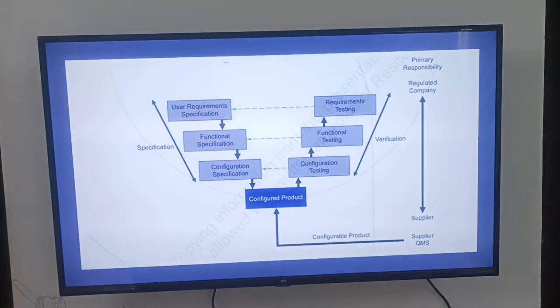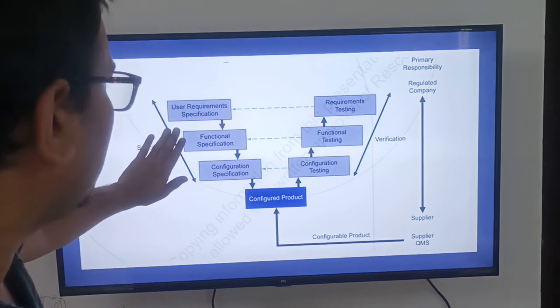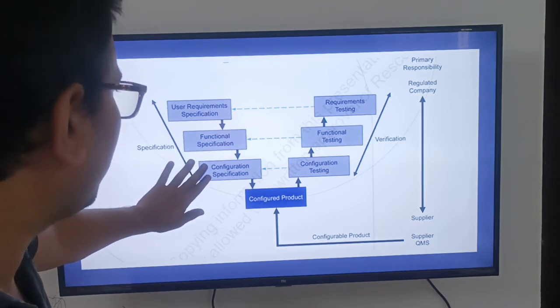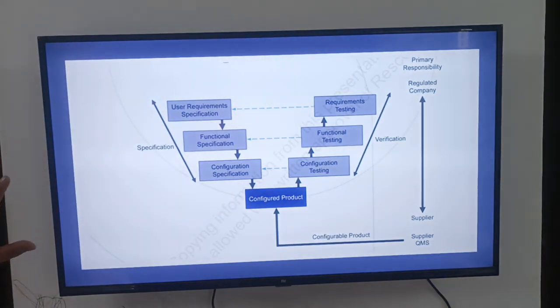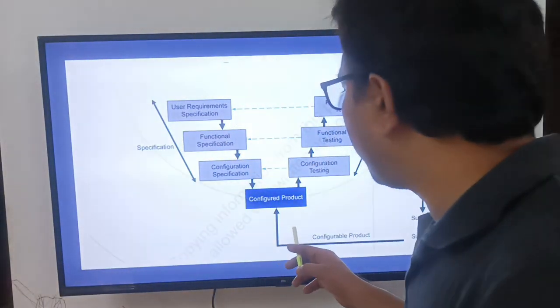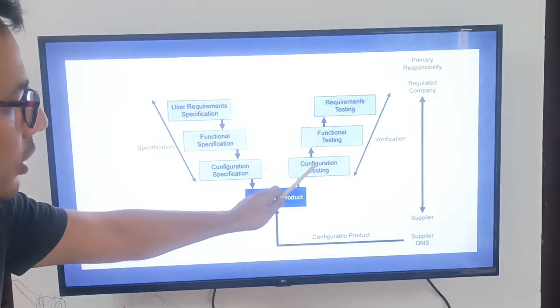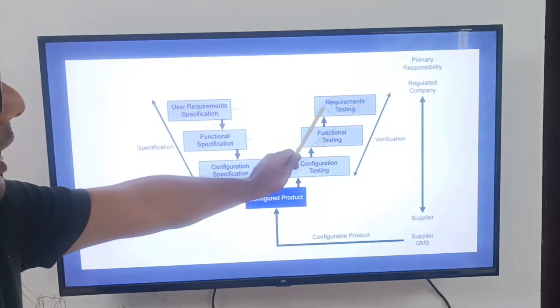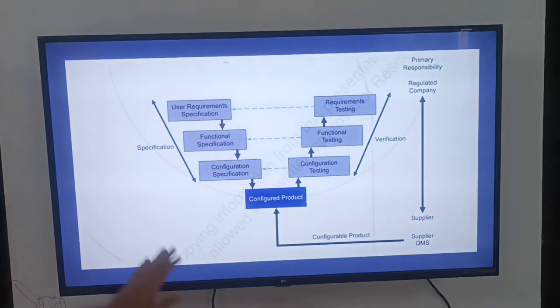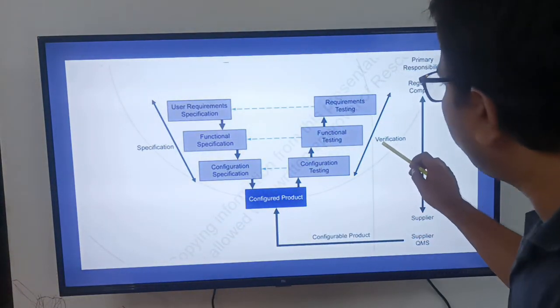Here is a diagram showing how we deploy Category 4 software. When we establish the software category, first we have to make the URS, then functional specification, then configuration specification. According to those specifications, when we receive the configured product, we have to do configuration testing, functional testing, and requirement testing — verifying against the specifications we made.